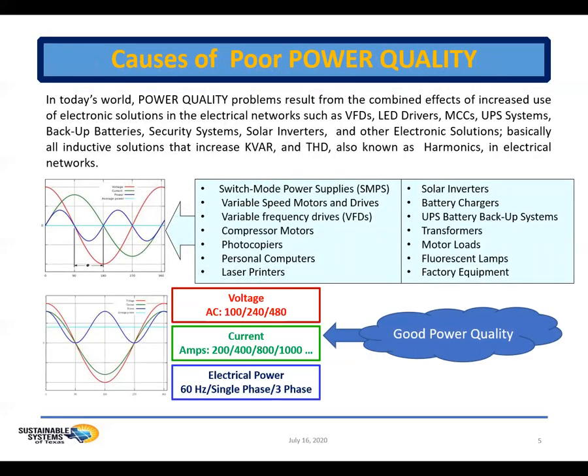Next, I want to talk about the causes of poor power quality. In today's environment, in the modern world, it's all the devices that we've installed in our plants that are actually causing the poor power quality problems. As you can see from this top graph, modern technologies or the combinations thereof cause the frequency of the electric power to shift out of phase. And these phase shifts result in heat loads within the equipment in the system, leading to their premature failure. And in the bottom graph, what you'll see is when you have good power quality, your power will be more in phase.